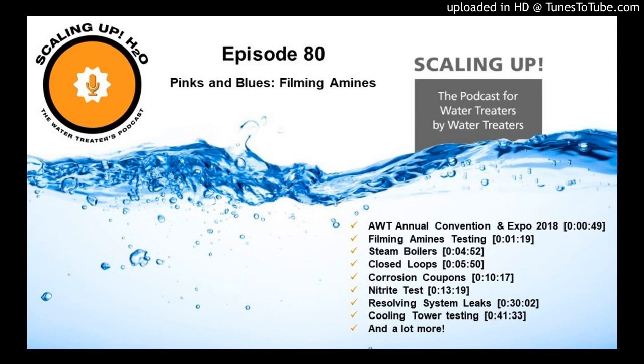It's that beautiful, dark, dull magnetite color that we all aspire to get, because we know that it's allowing us to corrode the metal so we don't corrode the metal further. I love saying that to new water treaters. It just makes their heads pop off. So we got a picture of that up there, and we also have pictures of the filter bags every single time we service this account. We were servicing it on a weekly to every 2-week basis, and then we dropped down to every month.